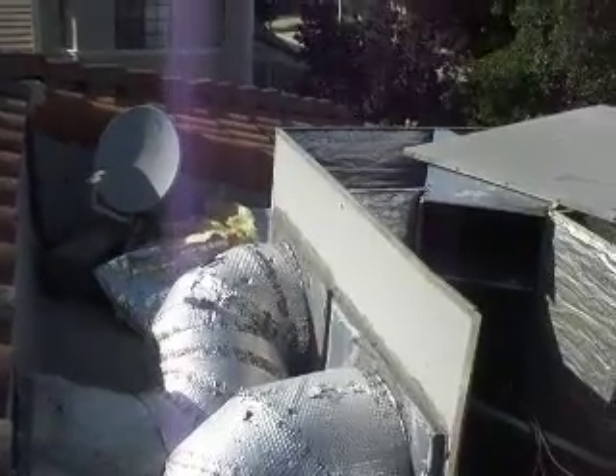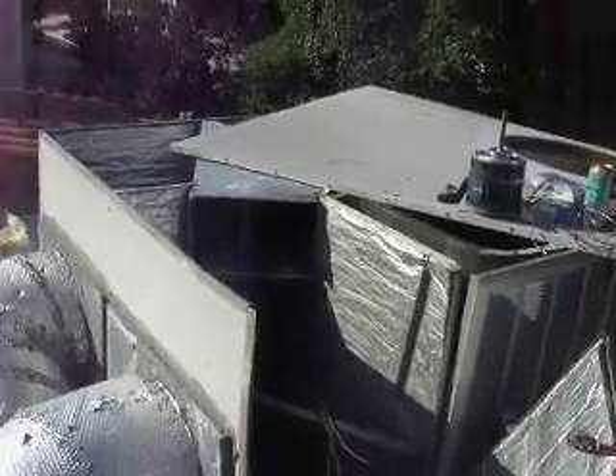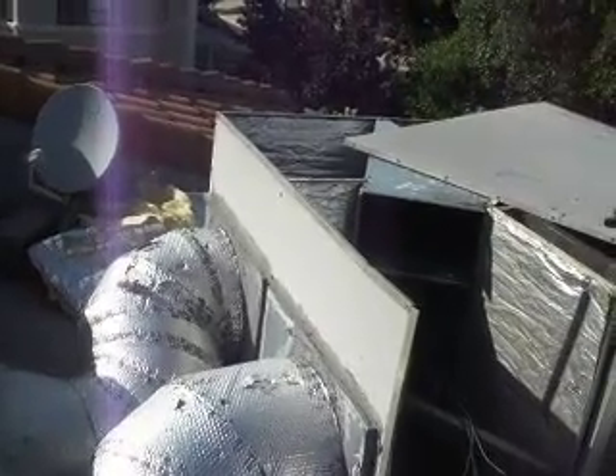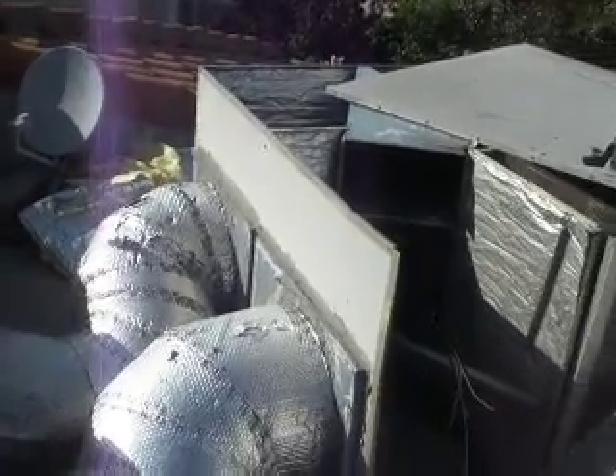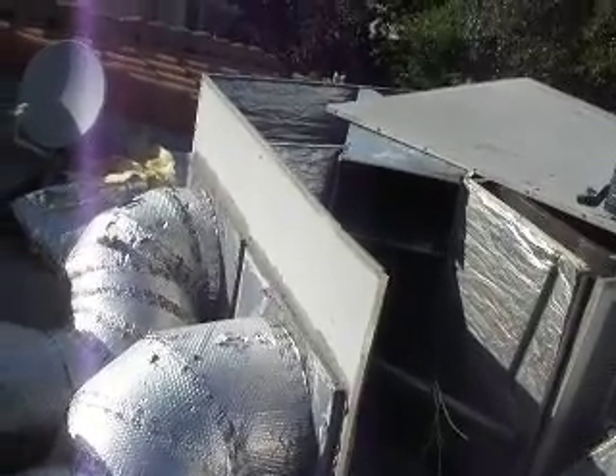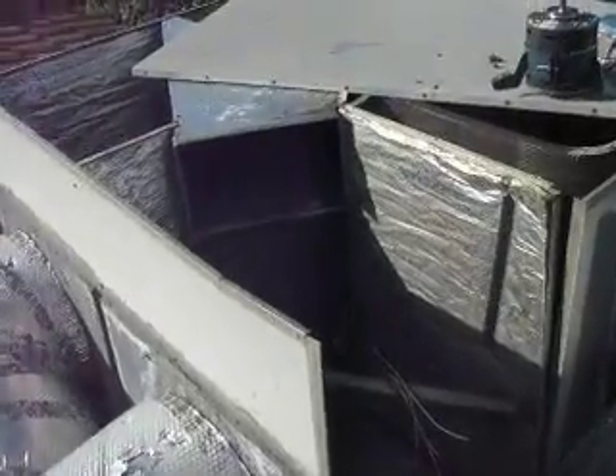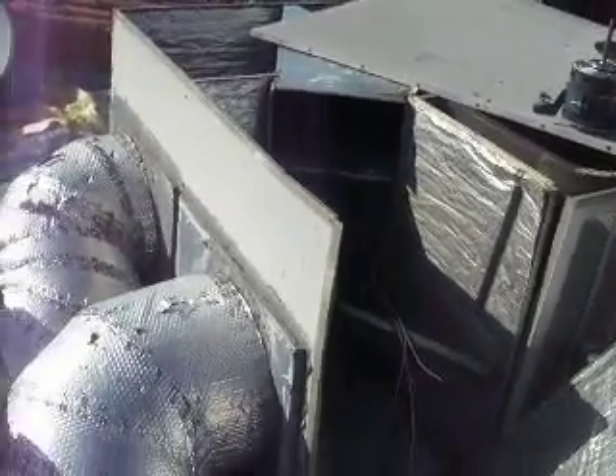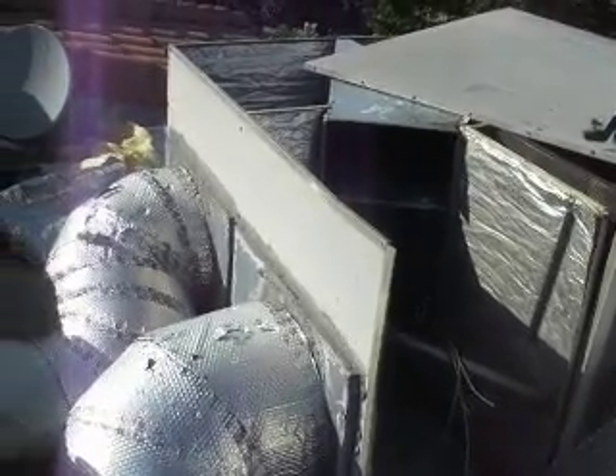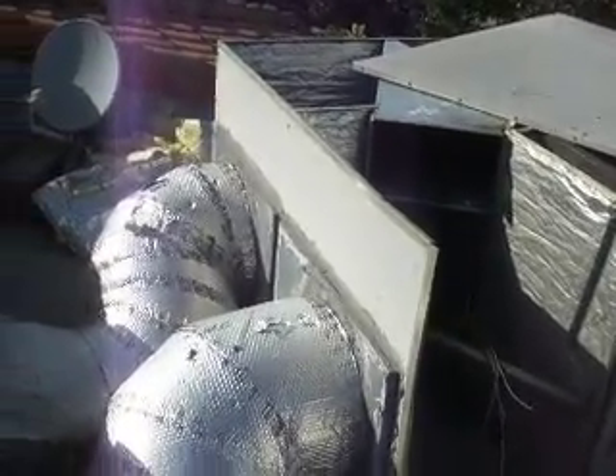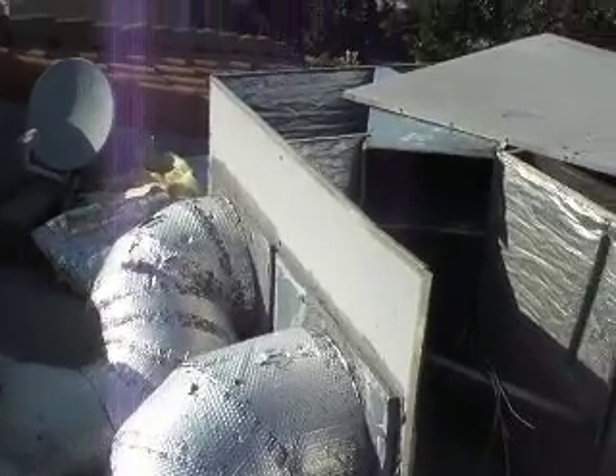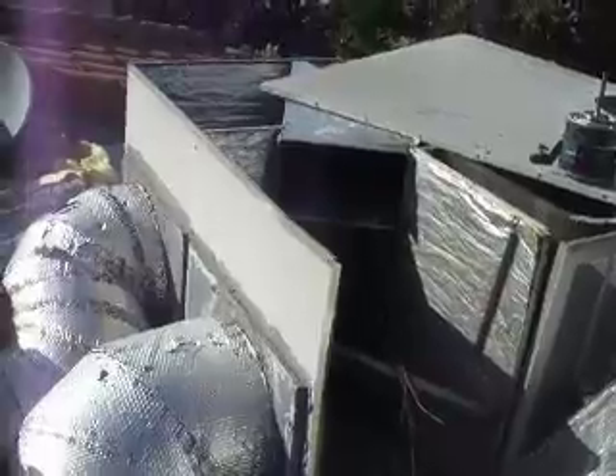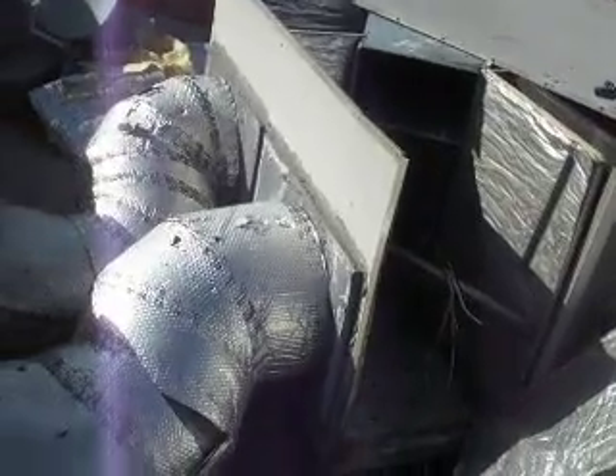This one right here has a cracked heat exchanger on the heater. We did order one, but unfortunately the replacement heat exchanger's flange is a little bit different, and what they want you to do is take this other header piece out where it goes up through the blower compartment and replace all that. It just doesn't really warrant the repair and the time on this unit. But I do have it, and I would really recommend replacing this unit.